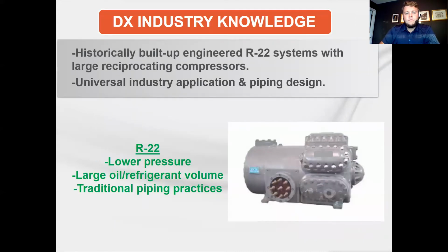So when I started back in 1970, R22 had just become the most common refrigerant, replacing R12 in HVAC projects. And at the time, it was the new high pressure refrigerant. Boy, there was just as much concern then as there was just recently when we changed to R410A. The photograph here shows a compressor. This is probably about a 60-ton reciprocating compressor. And a typical system back in those days would have a compressor like this mounted on the floor next to an air handler, maybe with a water-cooled condenser.